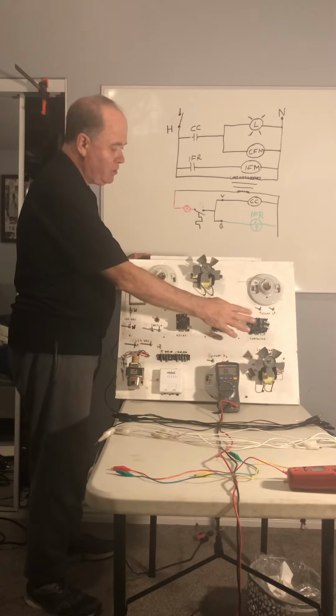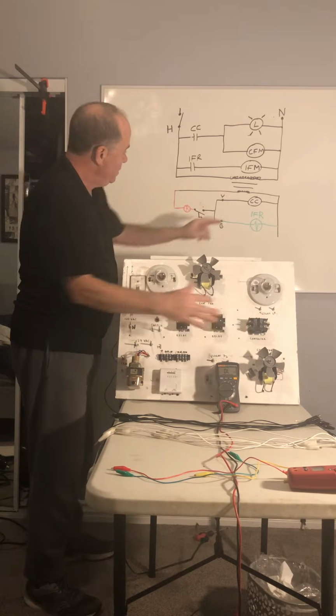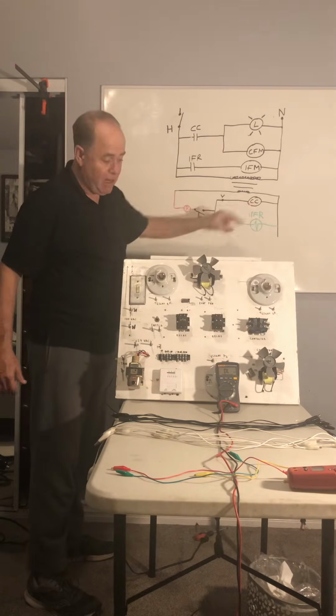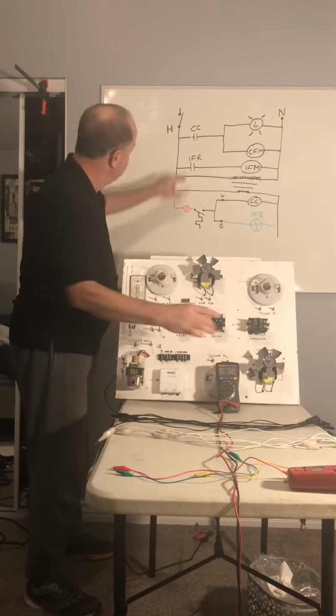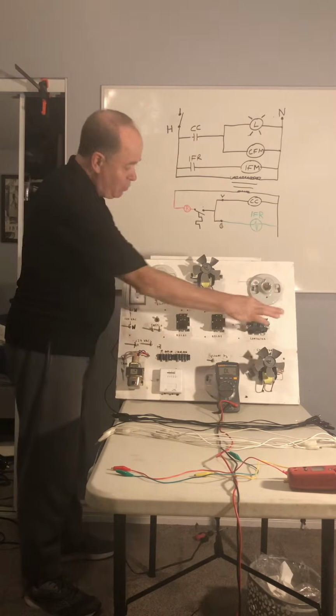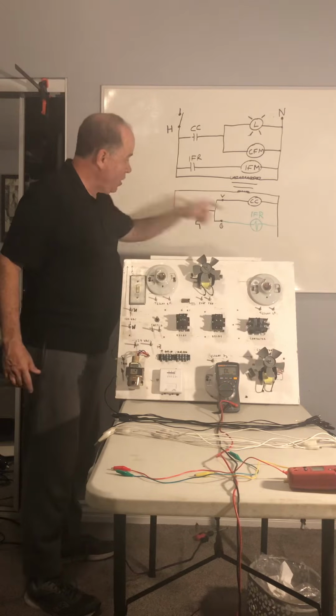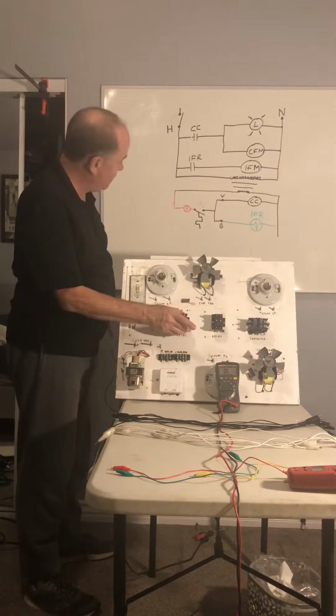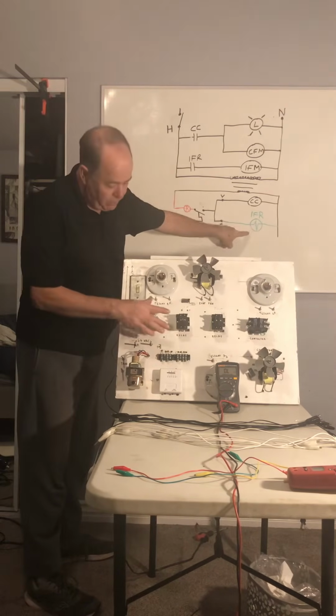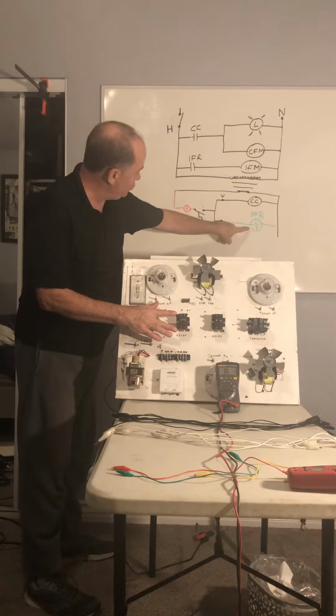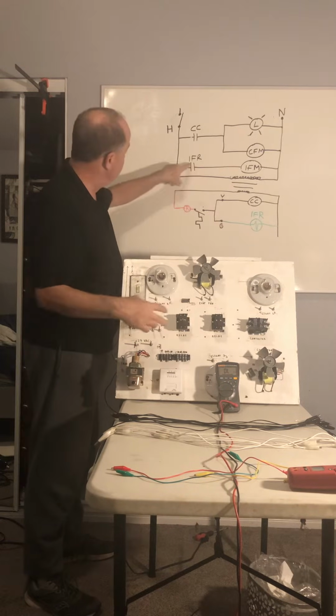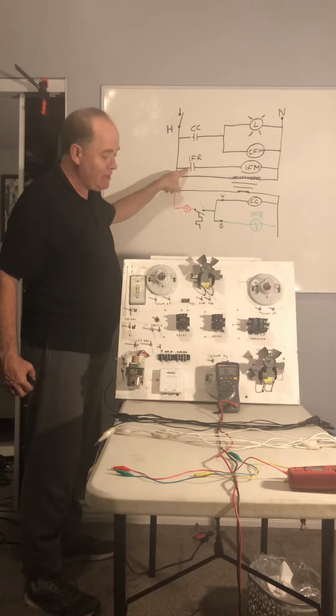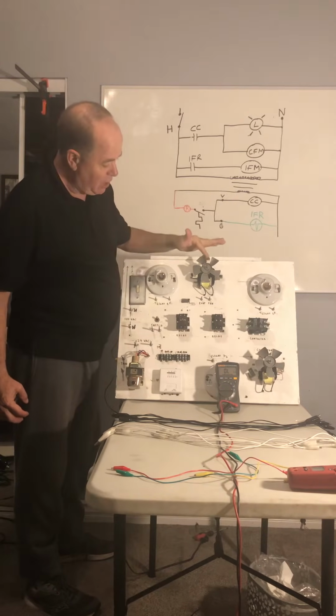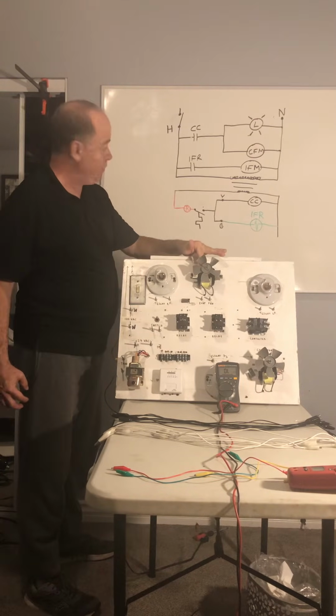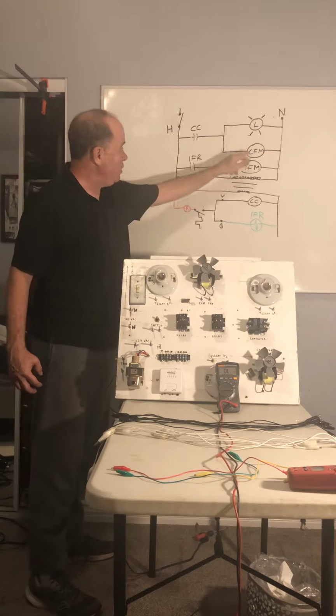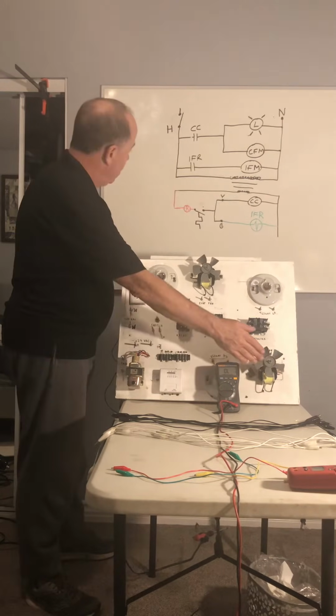Here's our contactor, and this is its coil, and this is the contactor coil on our schematic. Here are its contacts. Right here is a contact we're going to use. This is our indoor fan relay right here. This is the indoor fan relay coil portion of it. And then this right here is our indoor fan relay contacts. And then this is our indoor fan motor, evaporator fan motor right here, and our condenser fan motor right here.